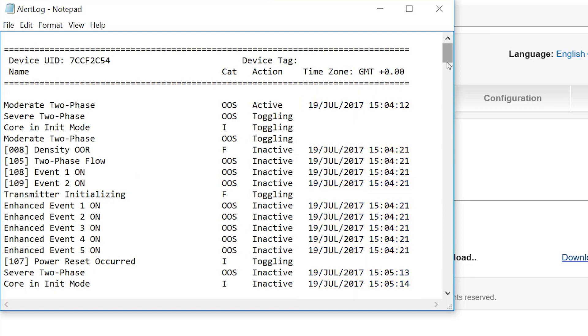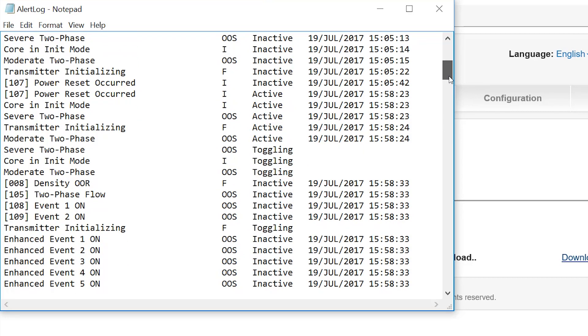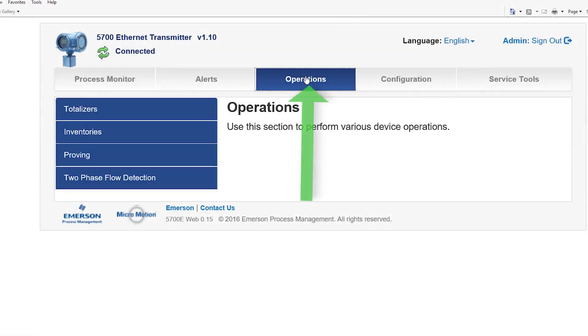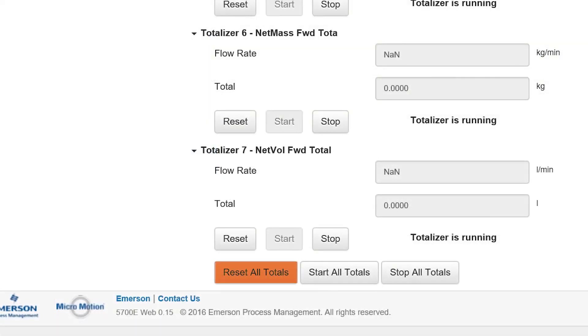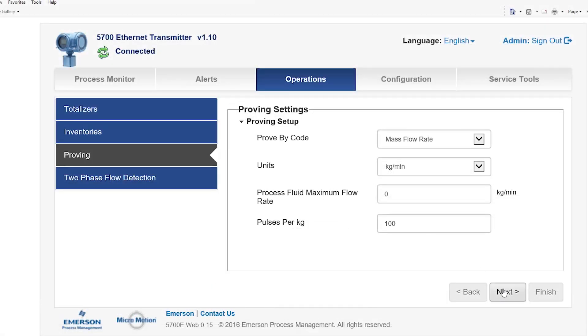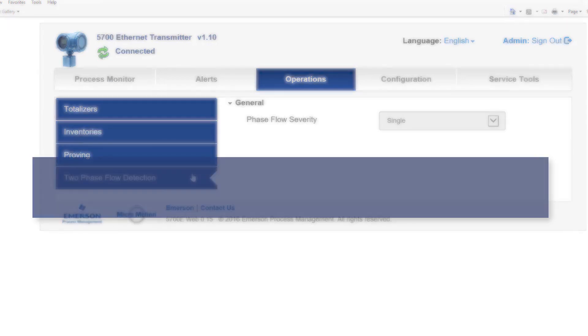The 5700 transmitter has an integrated real-time clock that is used to time stamp alerts, totalizer logs, and reports. Selecting the operations tab, the user can view totalizers and inventories, reset totalizers and inventories, access the proving setup wizard, and monitor two-phase flow detection: single phase (accurate and repeatable measurement), moderate entrainment (meter may be outside accuracy specification but measurements are repeatable), and severe entrainment (measurement is likely neither accurate nor repeatable).